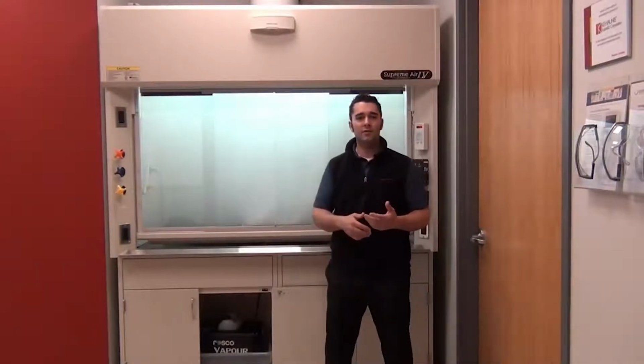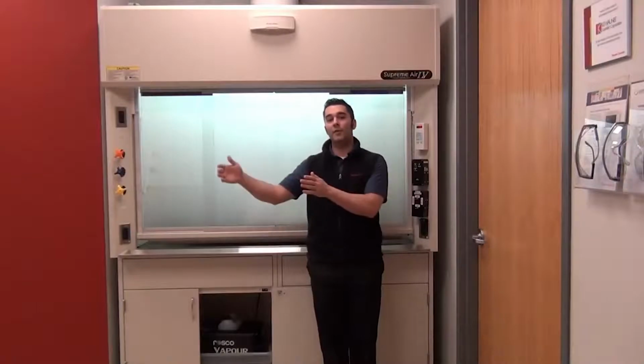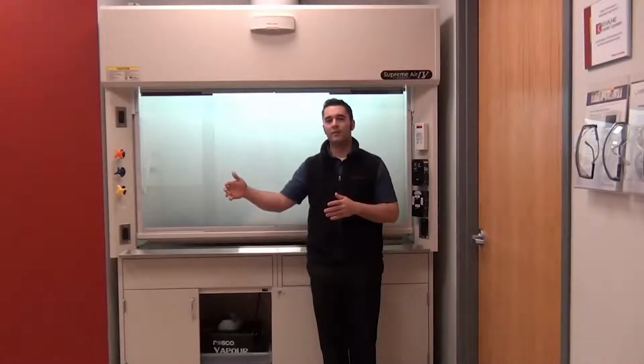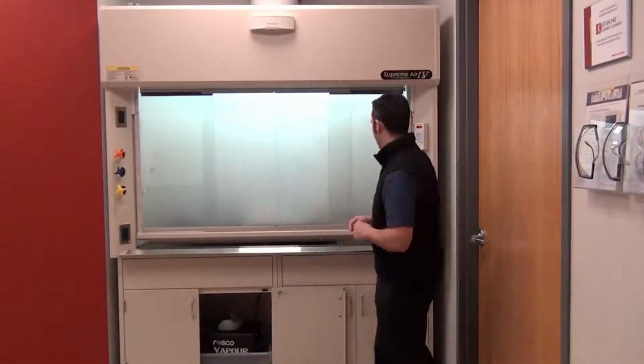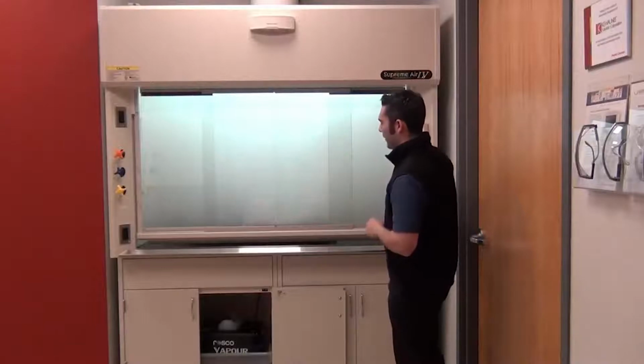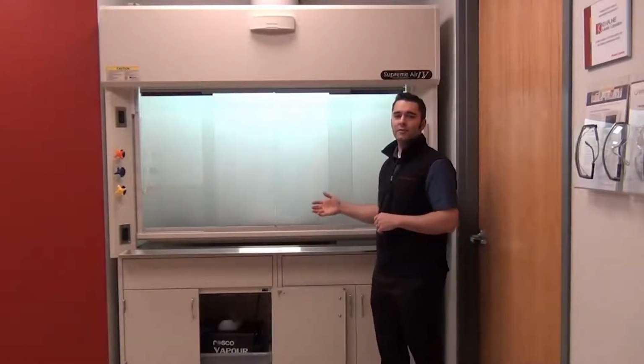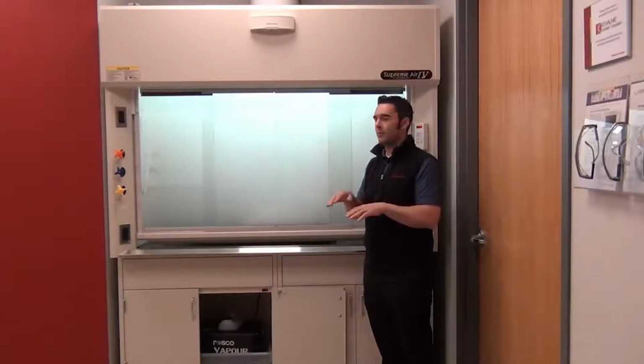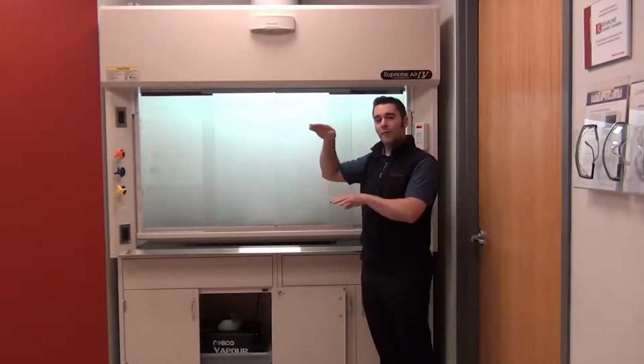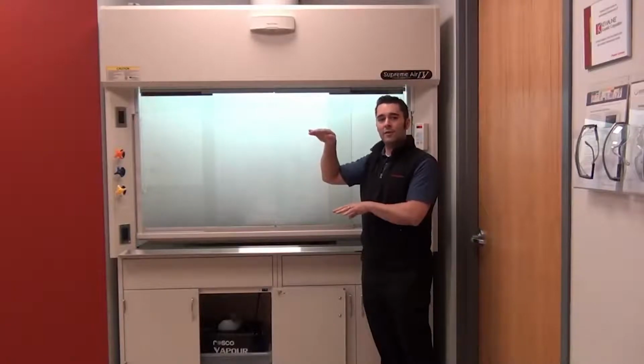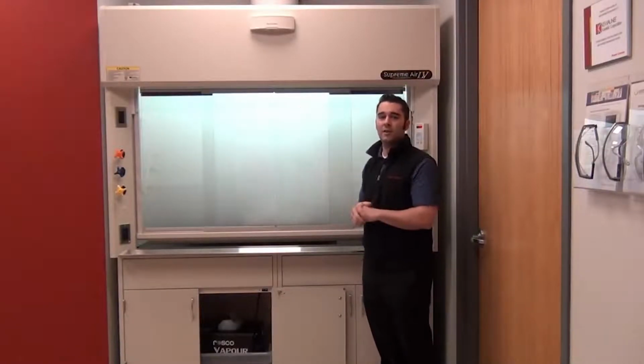Now we hear a lot in the industry that 3 second speed of response is good enough. Everybody says, well, the standards say that within 1 second you can start to move the airflow control device, within another second you can get to 95% of its position, and then within another second you can get the last 5% of its position. So that's a 3 second speed of response versus 1 second, and I can simulate how that looks by putting a delay inside of our valve here. So what I'm effectively doing is introducing a 3 second step delay, which will simulate my valve moving to achieve 95% of its command within the second, and then within the third second achieving the other 5% of its command.